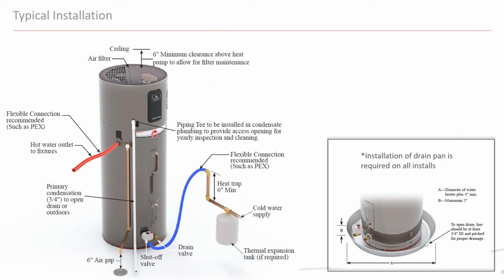The only other big difference that you guys are going to need is this condensation drain management. So it's a 3/4 inch PVC. It can either be converted to flex hose, or you can leave it as PVC, and it can be drained into a floor drain near the water heater. It is non-acidic because this is non-combustible. So a lot of times in retrofit applications, they will punch a hole to the outside of the wall and drain it out into a flower garden. Check with code just to make sure that is allowed. Sometimes they do need like a dwell tank or something to be able to capture that condensation. Again, it's rainwater. This is the same stuff on the outside of your can of Coke. If it's cold, it'll produce some condensation on it.